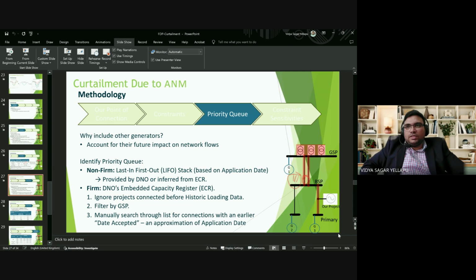As discussed, some projects are given non-firm generation connection offers, which means export of power from those generators is not guaranteed. That is based on the status of constraints. If there are some constraints, then they have to adjust their generation such that there is no violation of those constraints. That is the concept of non-firm offers. Those are associated with the last-in-first-out (LIFO) stack or priority stack as discussed before. This is provided by the DNO or inferred from the embedded capacity register, which is followed by each of these DNOs.